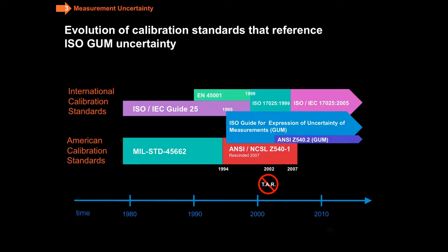And pretty much thereafter, all of the following standards that I'm going to show you refer to that. ANSI Z540.2, that is simply the American version or the Americas version, which changes some of the English for North American readers. 45001 and guide 25 merged together and became 17025 in 1999, and that continues today after the renewal in 2005. Another standard which came along in 2007 is Z540.3, and that one makes explicit references to the GUM.